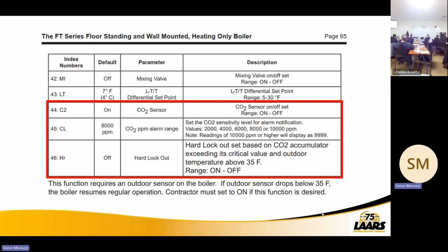So here, this is right out of the manual. Error code 44, it's defaulted in the on position. We're referring to CO, but this is done in CO2, okay? And you can convert those values if you needed to. But so it's defaulted in the on position. So we're looking for CO2 coming back to the cabinet, and we will lock that boiler out or give you an alarm.